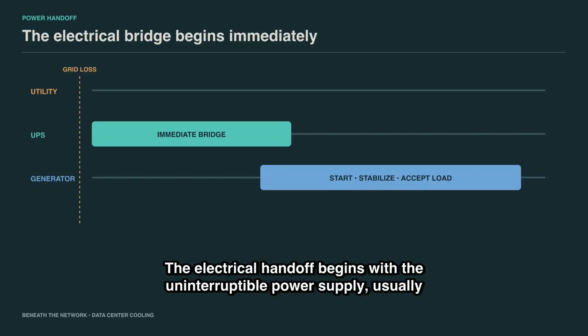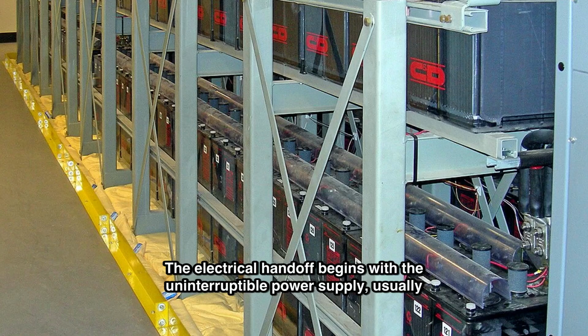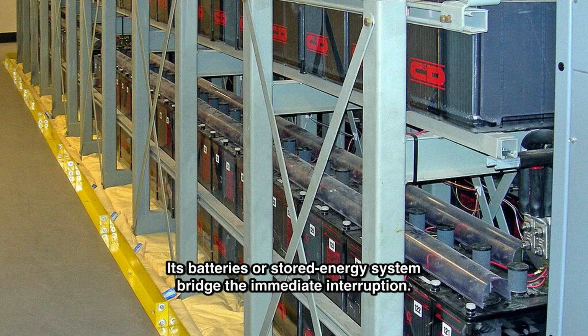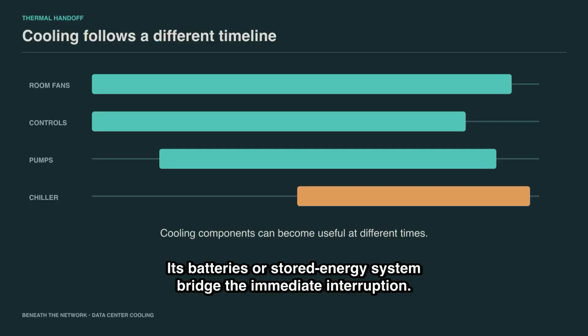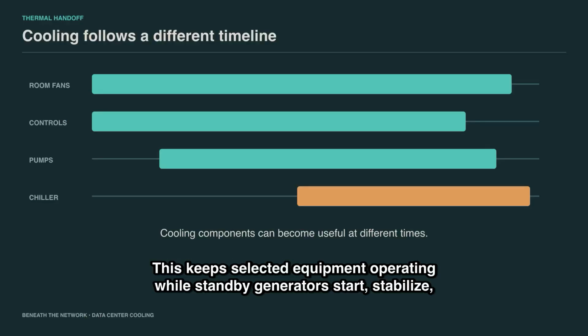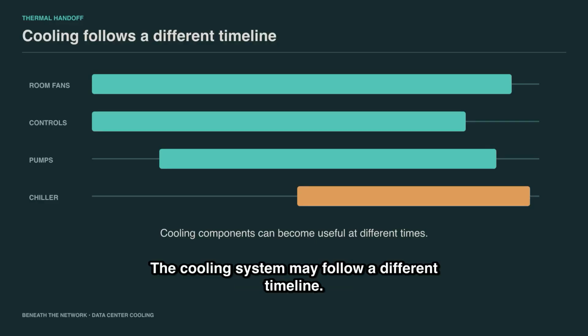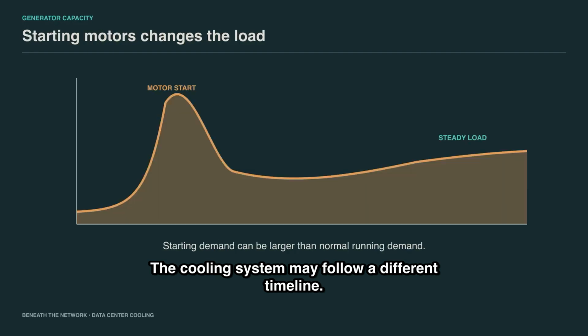The electrical handoff begins with the uninterruptible power supply, usually called the UPS. Its batteries, or stored energy system, bridge the immediate interruption. This keeps selected equipment operating while standby generators start, stabilize, and accept load. The cooling system may follow a different timeline.